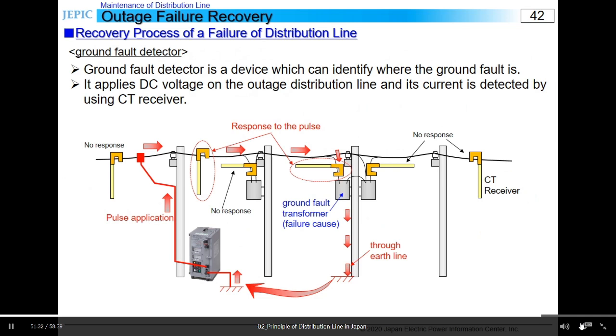After the outage area was finalized, that area would be patrolled, but some causes might be difficult to find visually. In such cases, we use the ground fault detector to find where the ground fault is. As shown in the figure, a ground fault detector is connected to the high voltage line and to the ground. It applies a DC pulse voltage to the high voltage line, and the pulse flows through a ground fault circuit, formulated by a ground fault detector, high voltage line, a ground fault point, and the ground.